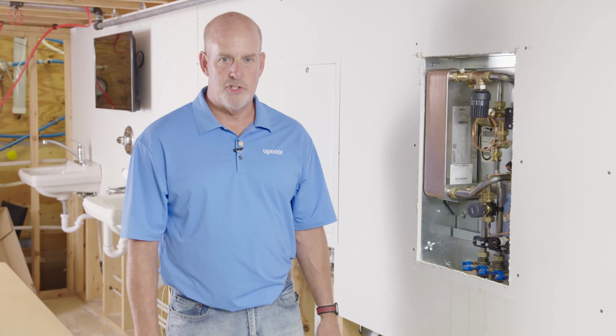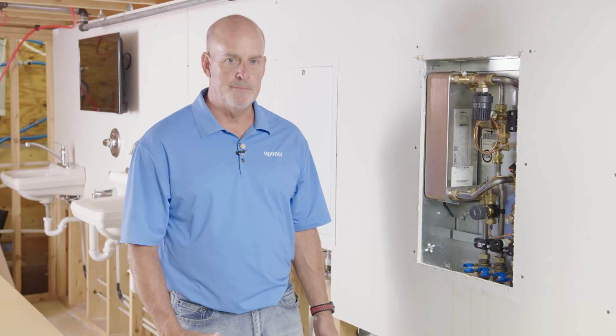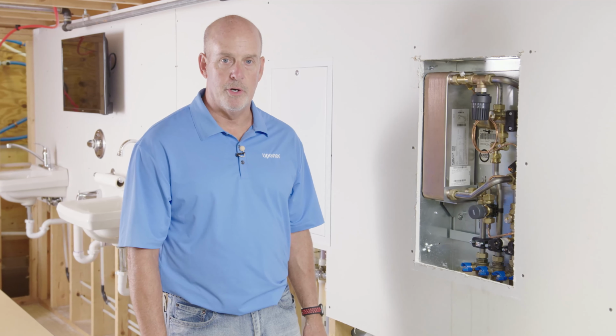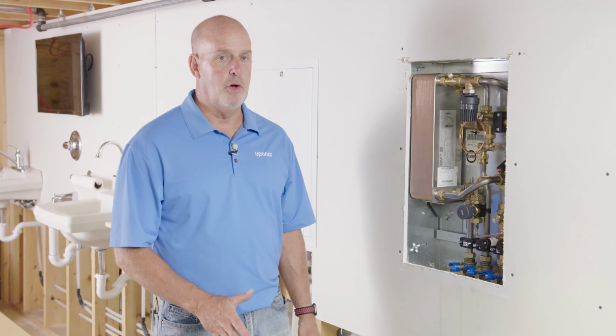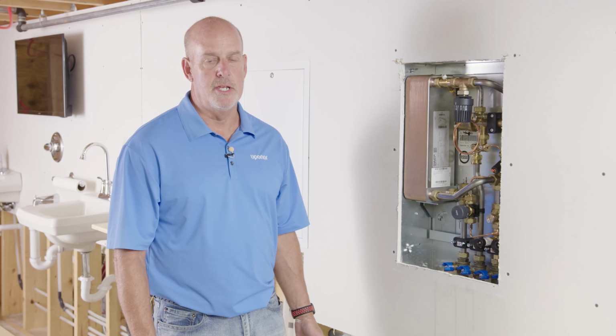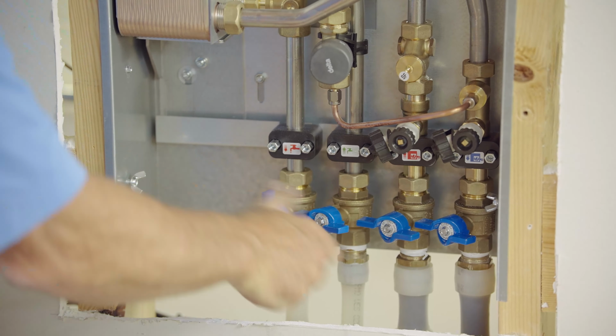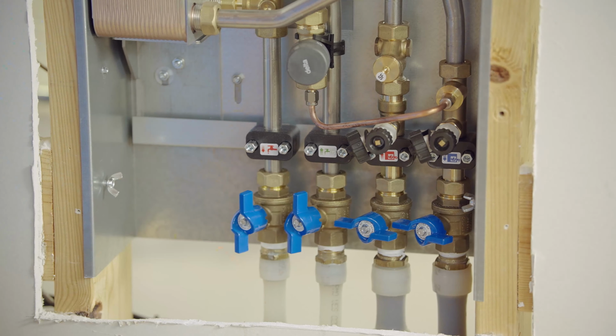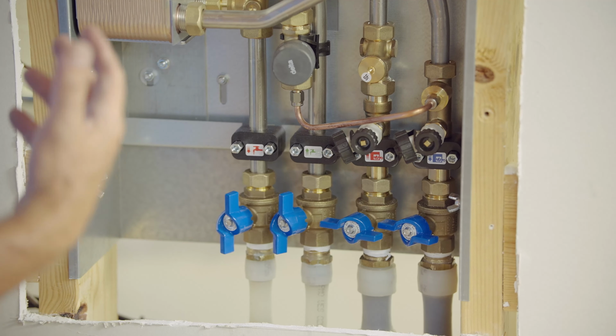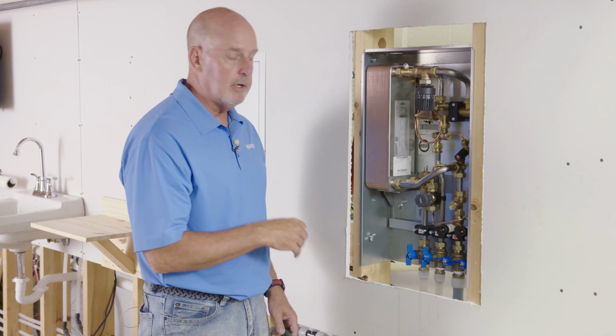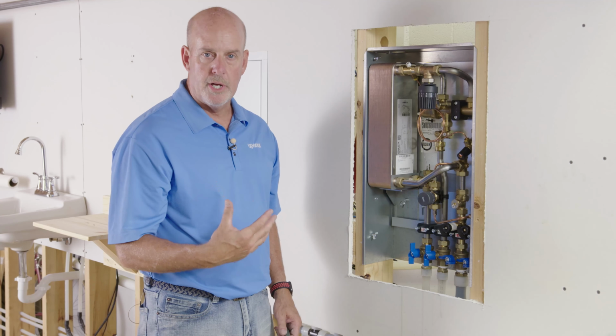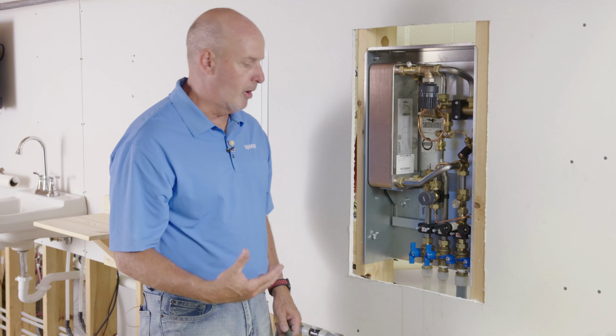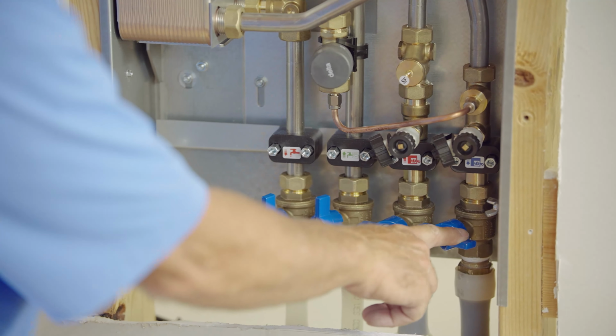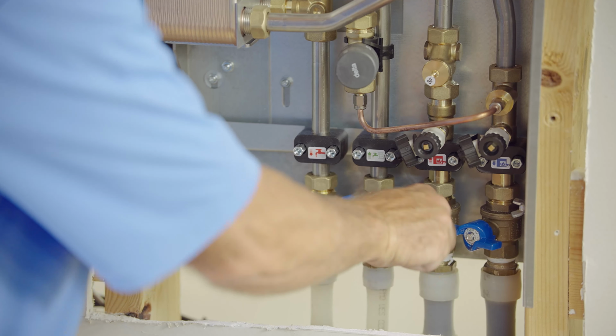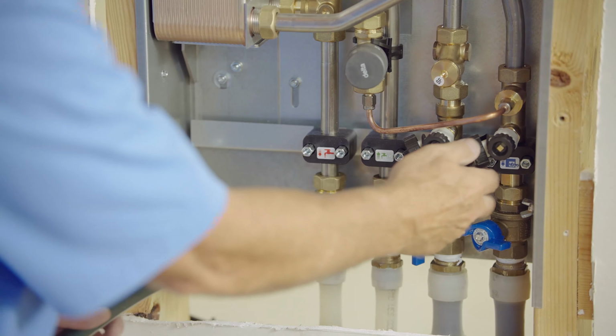Now that we've got the connections tightened and it's mounted to the back plate, we can reopen the valves to get ready for purging. Leave the last valve closed because that will help you assist in the purging procedure. On the plumbing side, the key thing to know is to get the air out of the cold water, open up the taps, and over a little bit of time, that'll actually get the air out of it. We'll leave the return valve on the hydronic side closed and open up the supply.